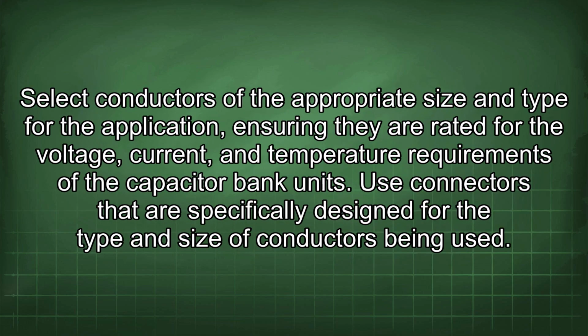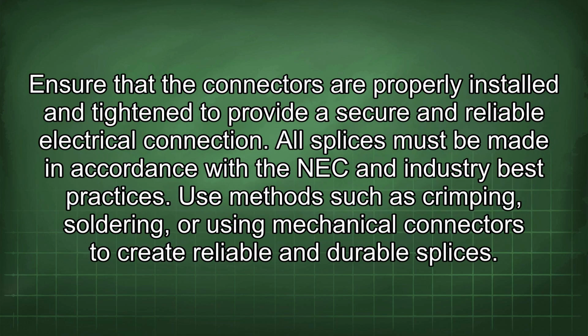Select conductors of the appropriate size and type for the application, ensuring they are rated for the voltage, current, and temperature requirements of the capacitor bank unit. Use connectors that are specifically designed for the type and size of conductors being used. Ensure that the connectors are properly installed and tightened to provide a secure and reliable electrical connection. All splices must be made in accordance with the NEC and industry best practices. Use methods such as crimping, soldering, or using mechanical connectors to create reliable and durable splices.